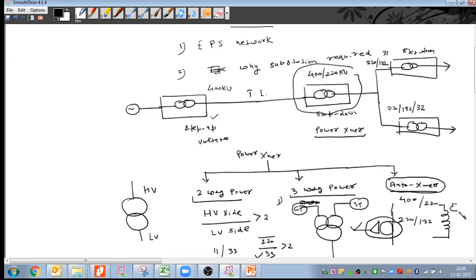So winding wise, we have one winding between the primary and secondary, and here we take the tappings. This is the HV side 400 kilovolts, this side 220 kilovolts, and here we have taken the tapping. Here we are putting some load to balance or to eliminate the third harmonic, and we connect it in delta for that. So if we have a substation where the voltage ratio is less than 2, for example 400 by 220 kilovolts or 220 by 132 kilovolts, in that place we will use an auto transformer type transformer.